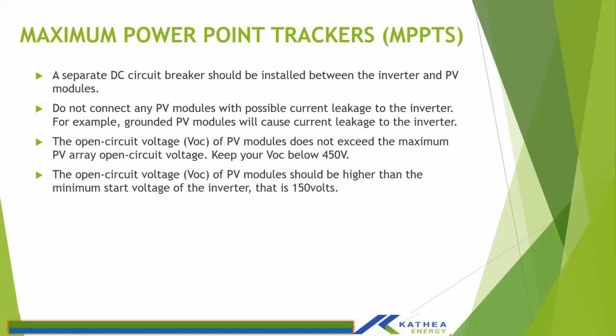So the maximum MPPT VOC is 450 volts, and the minimum is 125 volts, but the startup is 150 volts. So you should have a minimum of 150 volts for the MPPT to start working, a maximum of 450. However, when the MPPT is in operation, if PV drops below 125, then it will switch off. So when designing, your PV array voltage should range from 150 to 450. So if we use 50 volts for calculations, that's about a minimum of 3 panels and a maximum of 9 panels in a string if you are designing your string.